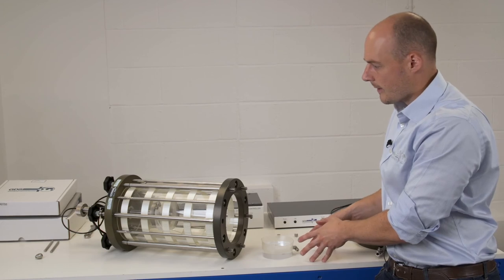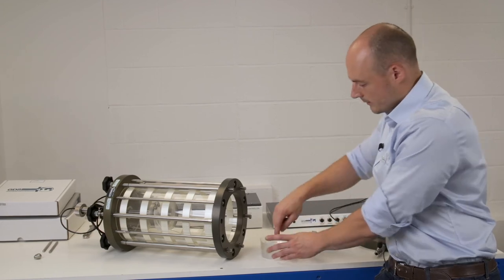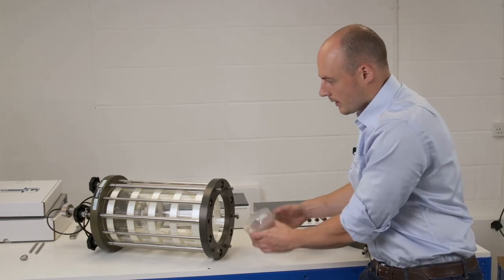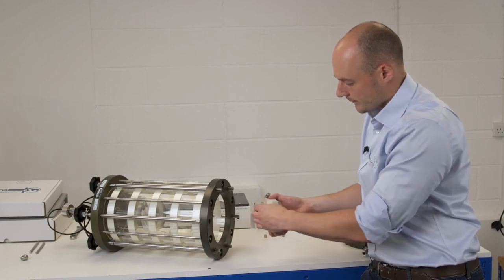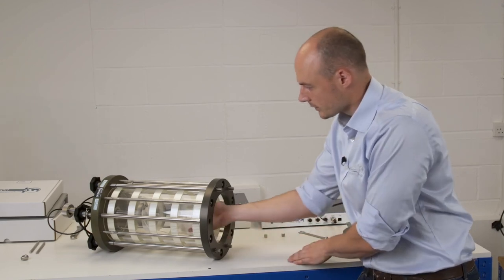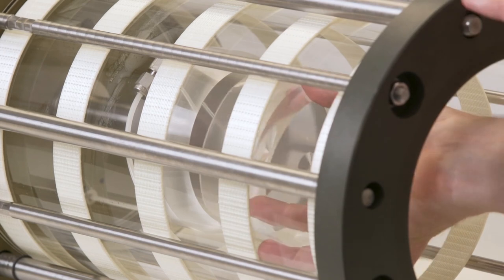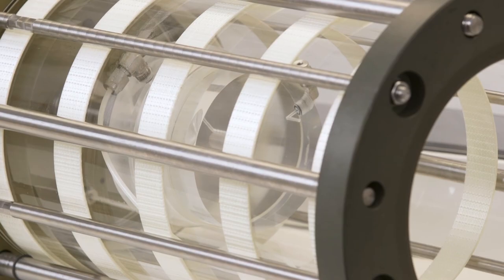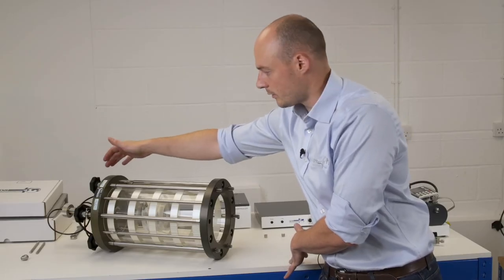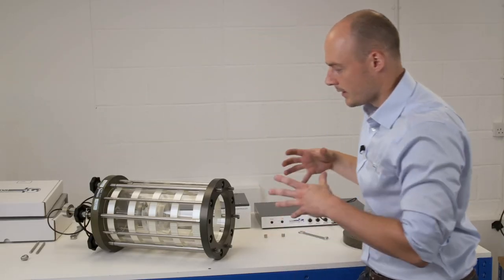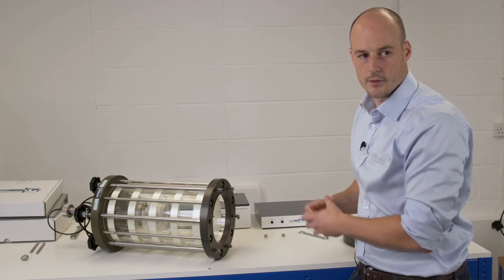When we're filling the cell, we'll bring the top cap and extension top cap piece into contact with each other, using the silicone grease to provide a nice watertight seal. And with the fitting on the top of the cell venting to atmosphere, this will create our seal and differential pressure connection.